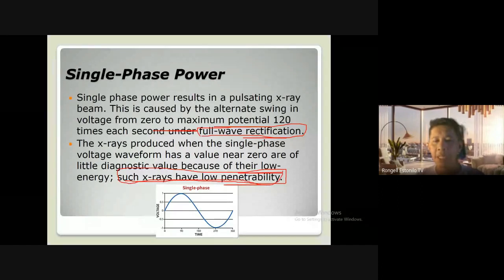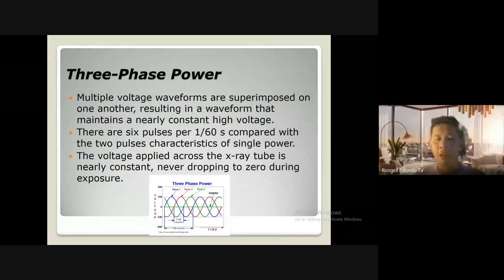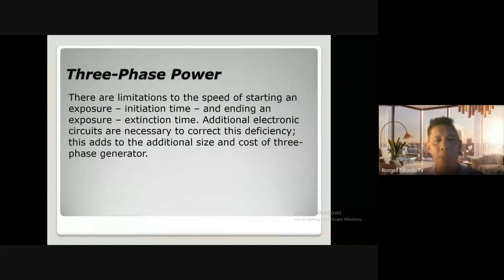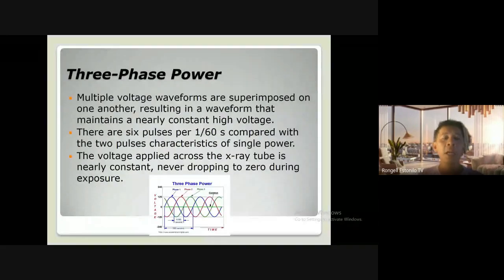So we have another option. We have 3-phase power. 3-phase power has two kinds: we have 3-phase 6 pulse and we have 3-phase 12 pulse. Multiple voltage waveforms are superimposed on one another, resulting in a waveform that maintains a nearly constant high voltage. So there are 6 pulses because we use 3-phase. Our sine wave is one phase, then our sine wave is 3.